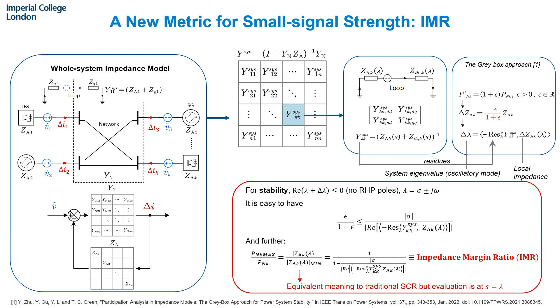It is equivalent in meaning to the traditional short circuit ratio, but the evaluation is carried out at s equal to lambda, where lambda is the oscillation mode of the system. In this picture, the blue arrow refers to the original impedance of the apparatus we are going to connect, and the small circle at the top right corner is the margin of variation it can have. Inside the circle is the instability area. The IMR is essentially the ratio between those margins, and it must be larger than 1 to maintain system stability. When it is larger, the mode is less sensitive to the connected apparatus.